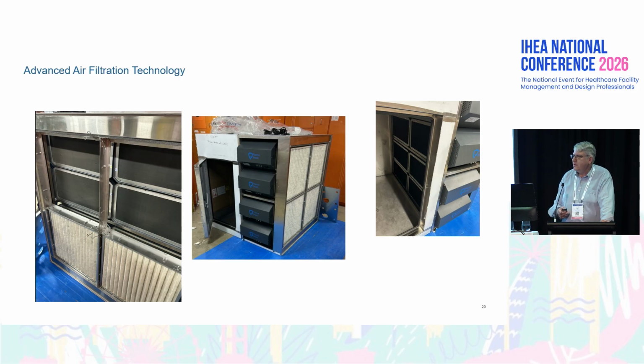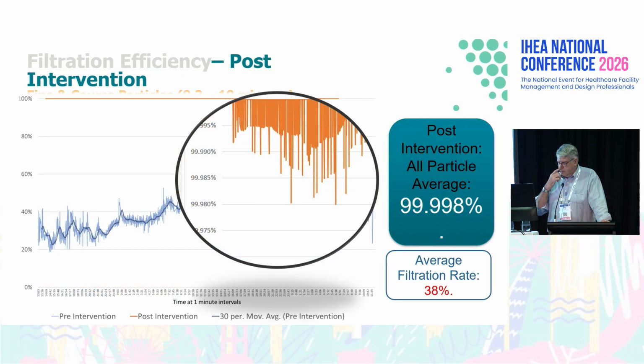For those who haven't seen it, the blue line there was the pre-install filtration rate. While we were talking about 98-99% filtration rates on your F8s, we were actually getting between 20 and 50%. Was that the filters, or did we have some bypass happening there? I don't think we'll ever find out, but if we were to do this again, we'd probably do some more measurements beforehand.